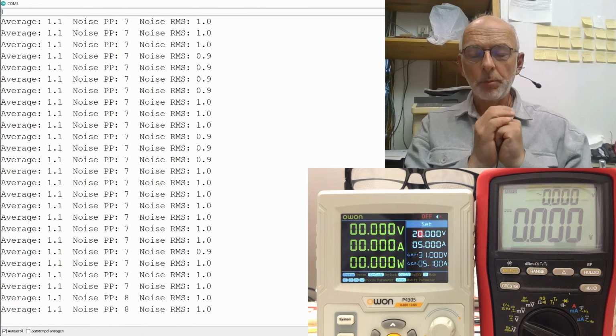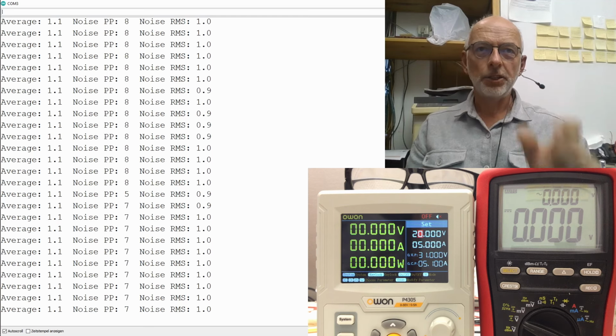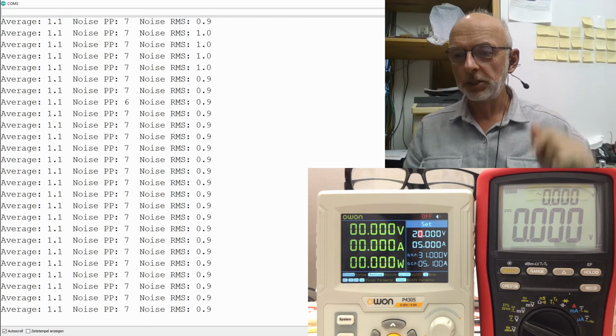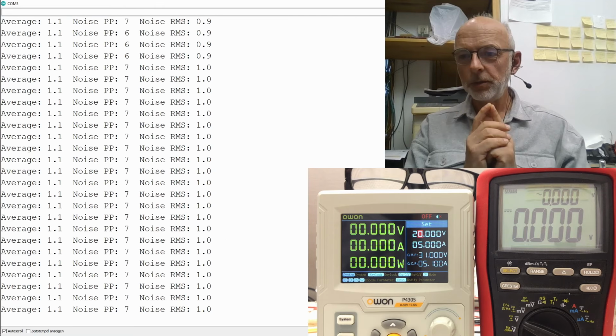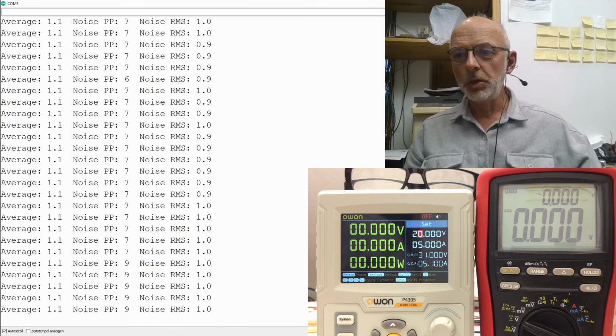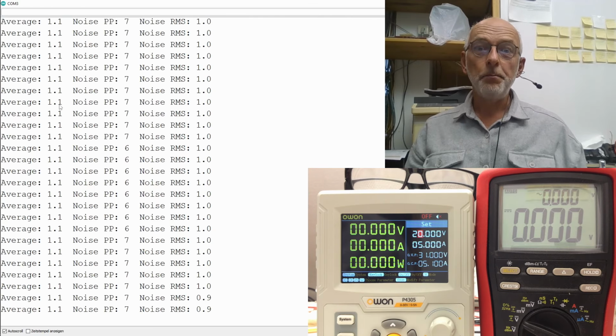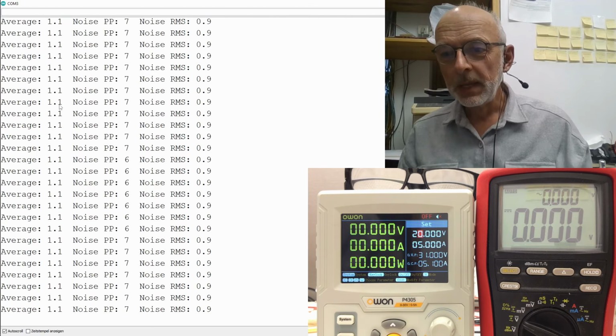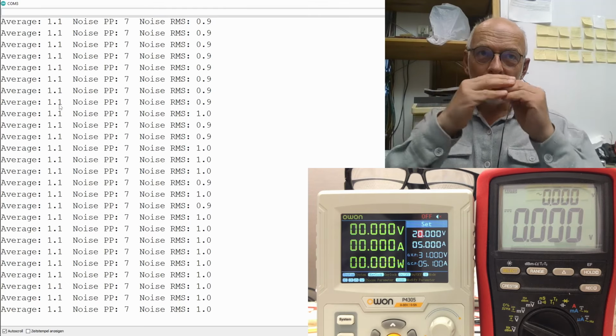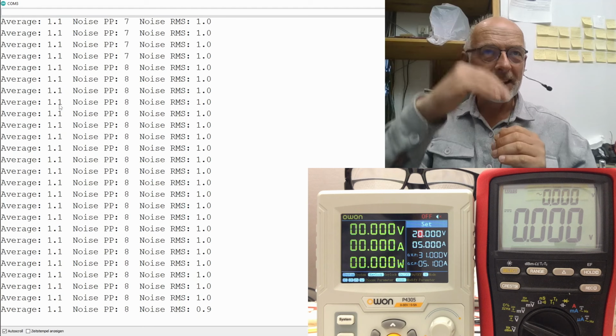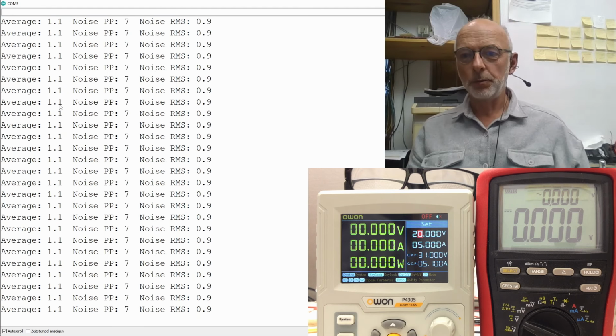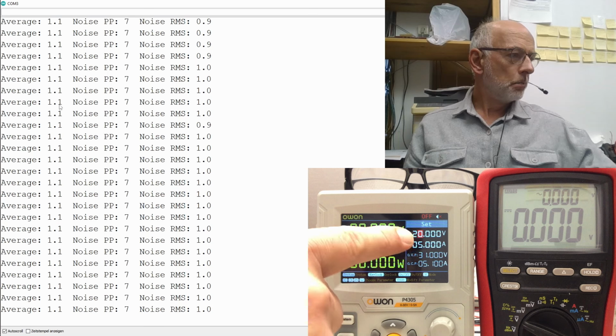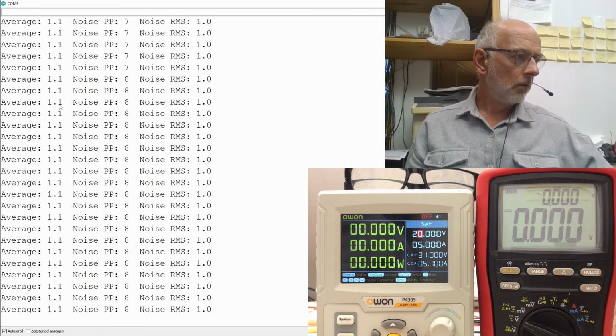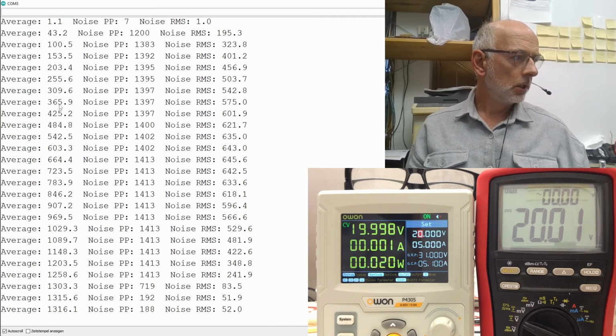Okay, now we're calibrating for voltage. I just changed the channel. We are sampling the voltage channel. And at the moment we are at 0 volts, where I don't want to calibrate, but I want you to note that our average is 1.1 LSBs, not 0 LSBs. That's because of the headroom of our op amps, it doesn't go down to ground with the output.